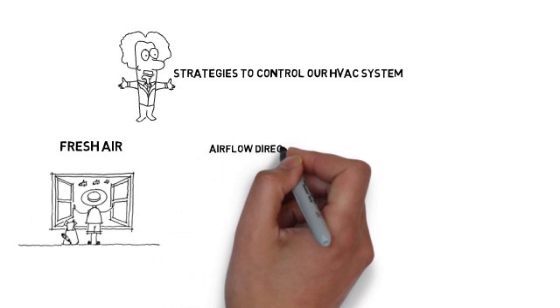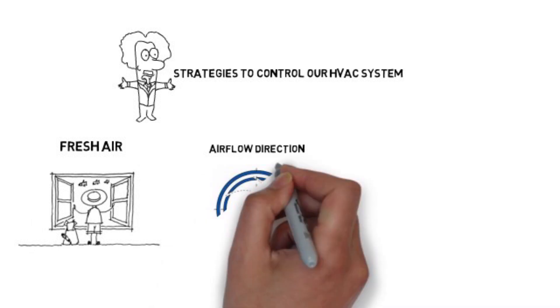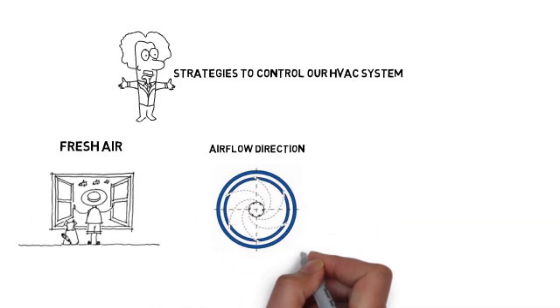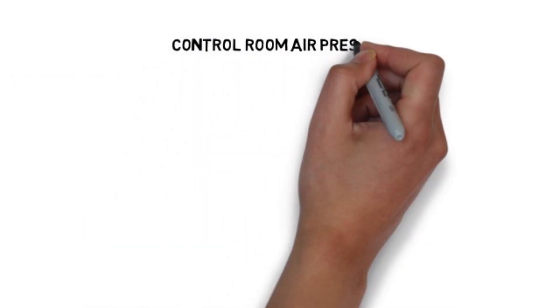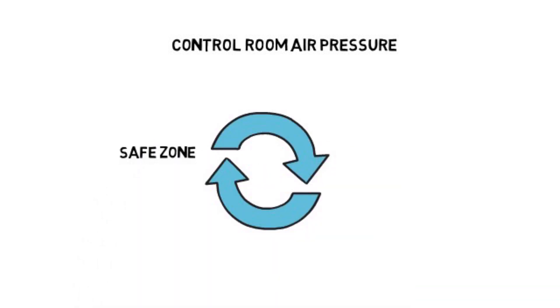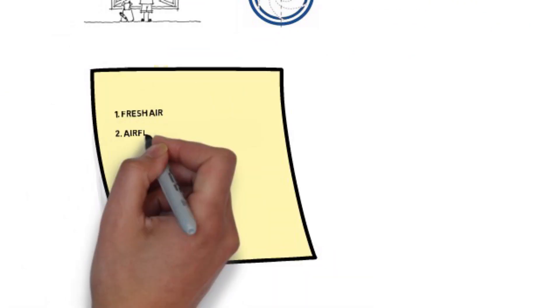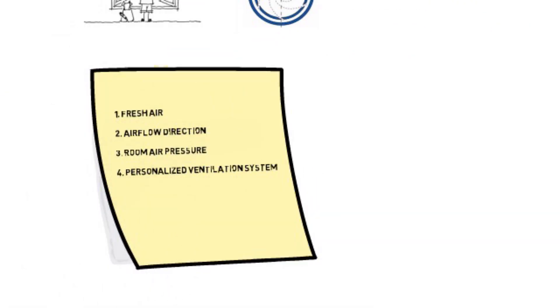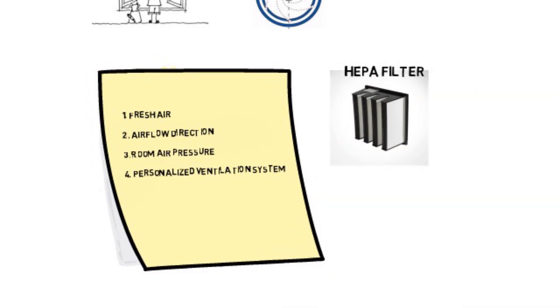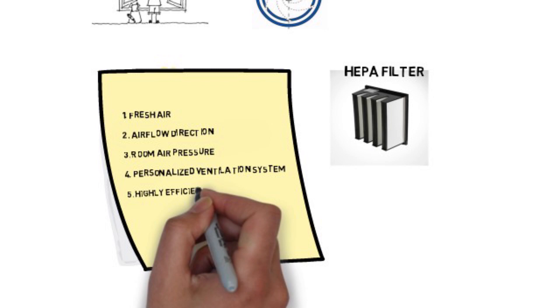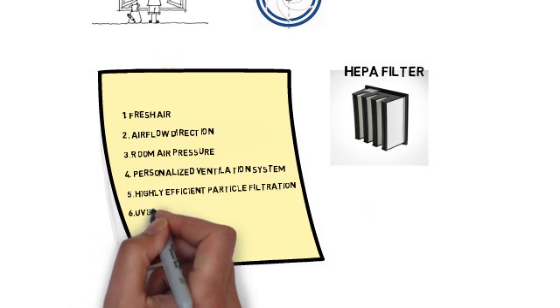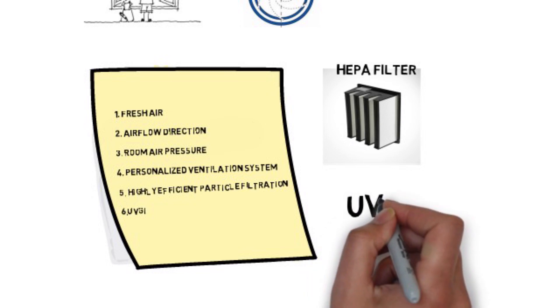Second, control airflow direction. You have to guarantee air flows from a healthy person to the infected person and not vice versa. Third, control room air differential pressure to make sure air flows from safe zones towards the unsafe zones in a building. The fourth strategy is using a personalized ventilation system that supplies 100 percent outdoor air, highly filtered, or UV-disinfected air directly to the occupant's breathing zone. Other strategies include adding highly efficient particle filtration to central ventilation systems and utilizing an ultraviolet germicidal irradiation system, or UVGI, to disinfect the air.